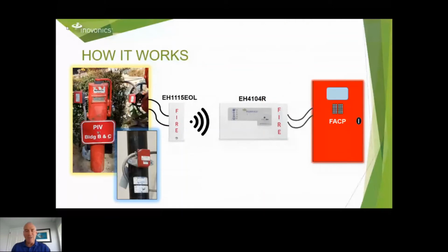So let's talk about this briefly. So let's say you've got a PIV, a post indicator valve, whether it's across the building, across the parking lot, or across the street. And there's no wire going to it from the panel, but it needs to be monitored. So our transmitter would take that contact, and then when that valve or switch activates, it reports to the receiver, which would be connected. Now there's 5 relays: alarm, tamper, battery, missing, and jam, that would go into the fire alarm control panel.